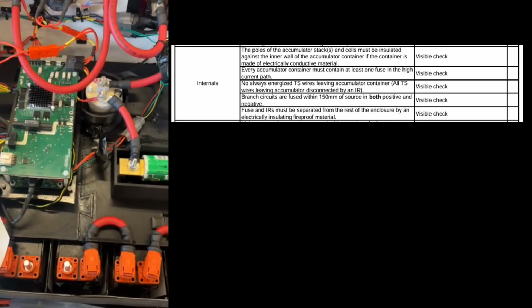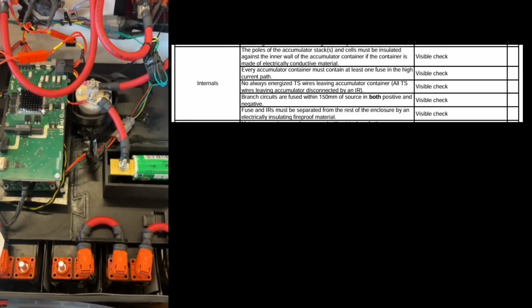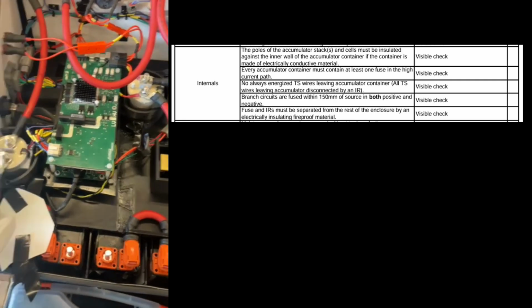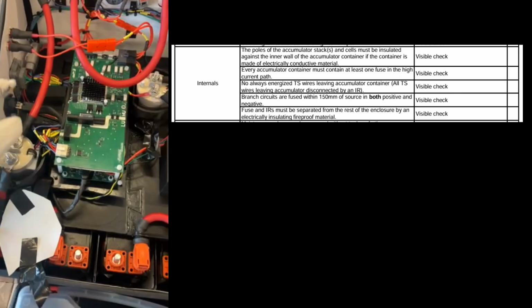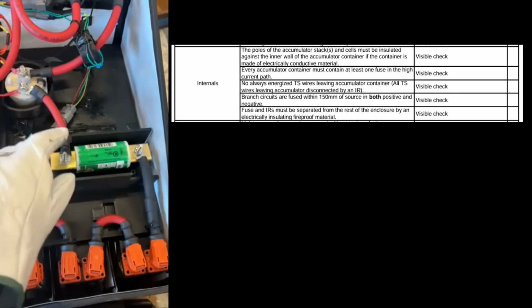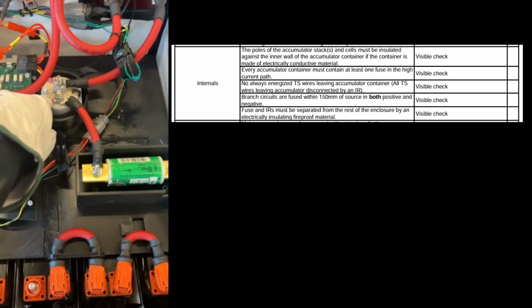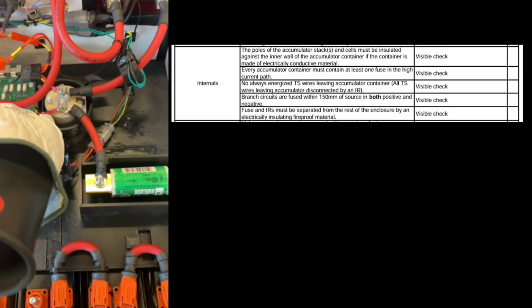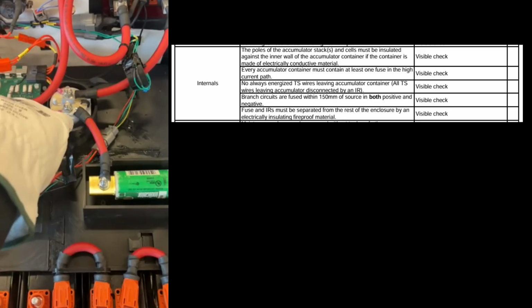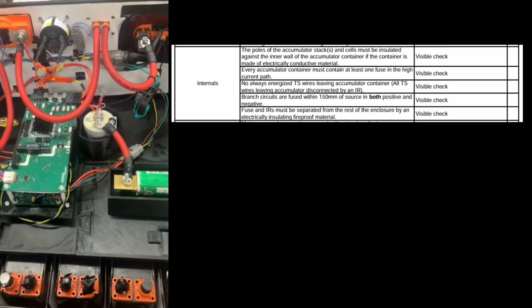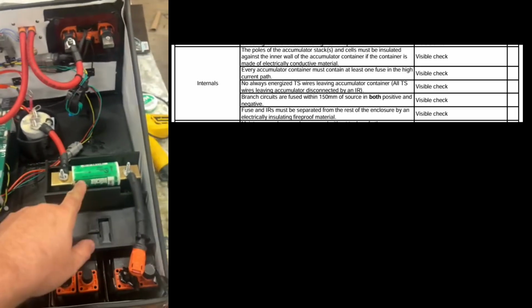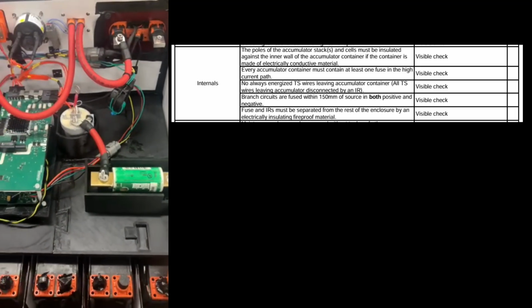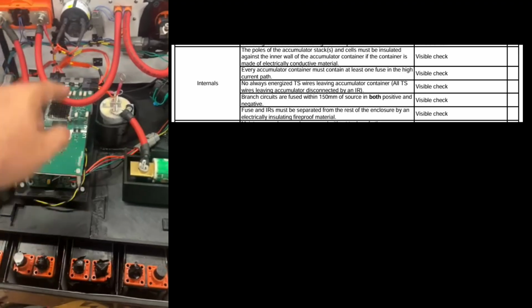To demonstrate that no tractive system wiring leaves the accumulator without going through the AIR first, you can see this AIR has no wiring connected to it other than the main tractive system wiring. Same for this fuse. The only thing before the AIR is this sensing wire, what we call HV plus on the unswitched side of the AIR, which goes directly to our HV sense/AIR control board. All of our wires are fused either by this main pack fuse for our tractive system wiring, or by fuses on boards like these.